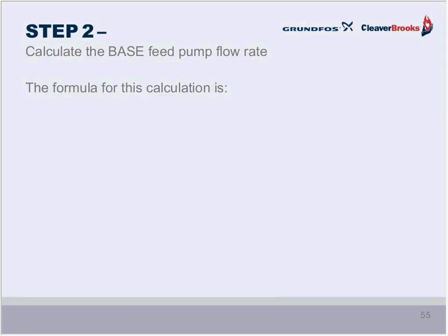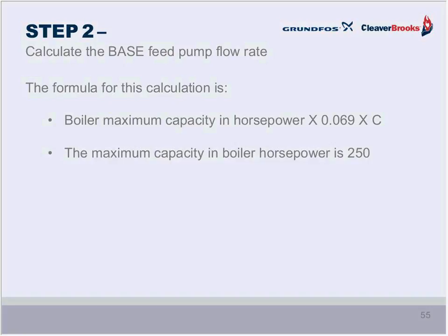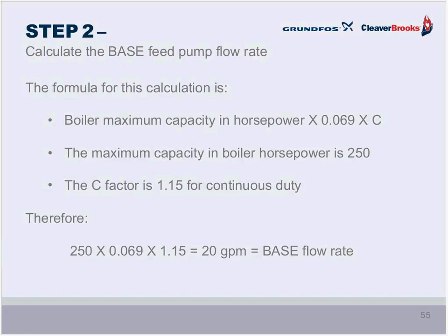So the first thing we need to do is to calculate the base flow rate. And we calculate that base flow rate using this formula: the boiler horsepower times 0.069 times a factor, which is C. That C factor varies. It is 1.15 for continuous duty, and it's much higher for intermittent duty. So we do the math here, and it comes out to 20 gallons per minute. That's our base flow rate.